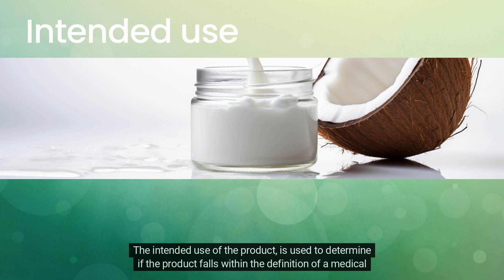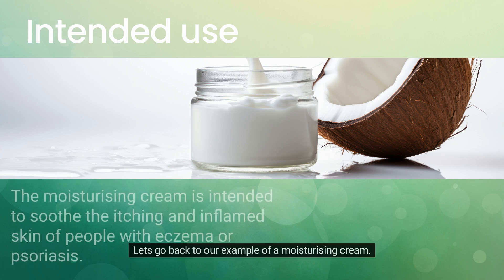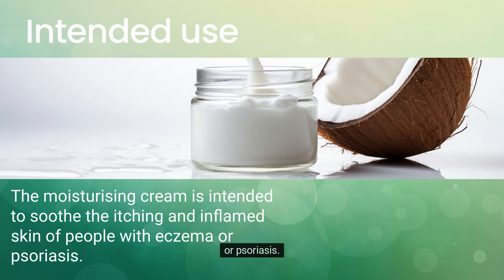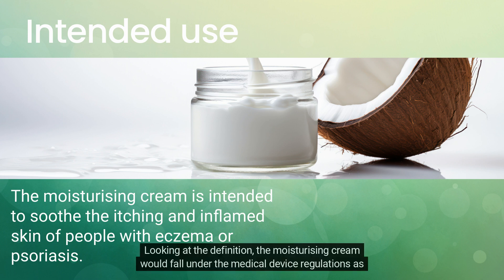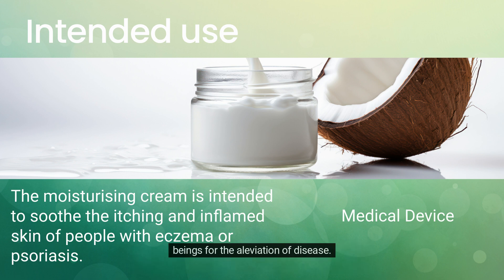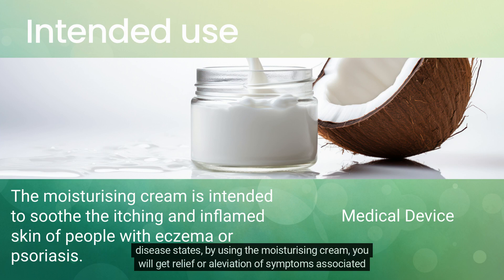The intended use of the product is used to determine if the product falls within the definition of a medical device described in the regulation. For example, if a moisturizing cream is intended to soothe the itching and inflamed skin of people with eczema or psoriasis, it would fall under the medical device regulations. This is because the cream is a material intended to be used alone on human beings for the alleviation of disease, as eczema and psoriasis are disease states.